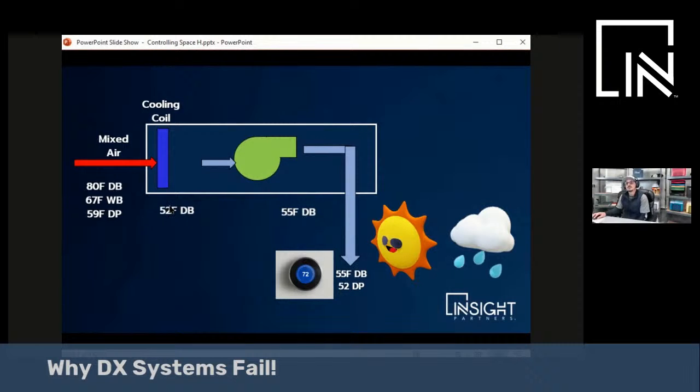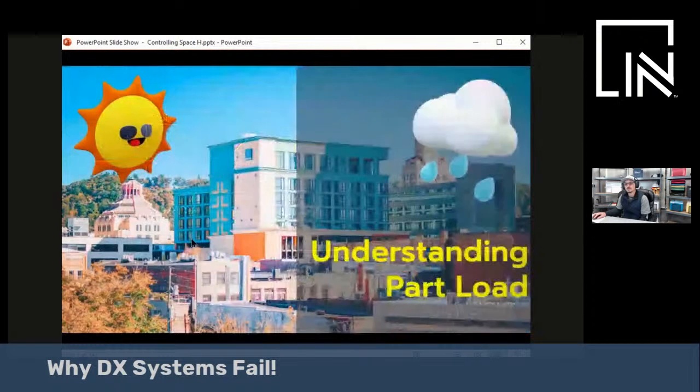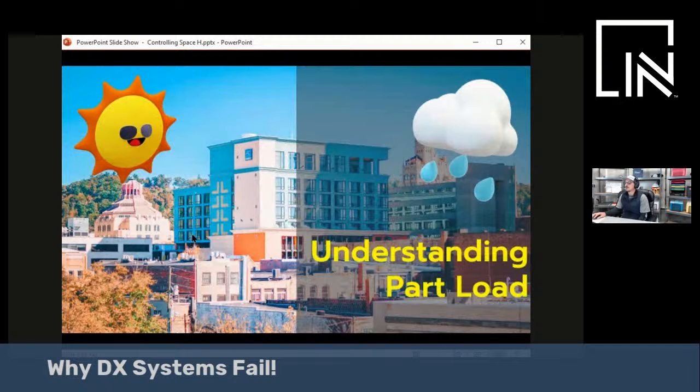At part-load conditions, if you're not running the evaporator coil, you're not dehumidifying. And therein lies the problem with controlling humidity at all load conditions. To understand this scenario, you just have to understand part-load.